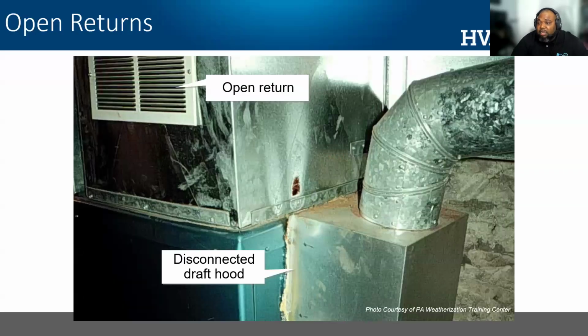It could be a combination of things, like something self-inflicted, maybe a customer cut an access hole in the return air, and they have exhaust gases that are coming back, being overpowered from my exhaust system and being pulled into my return air system. Again, these are things that you capture with testing, and if you didn't test, you wouldn't know that they were there.